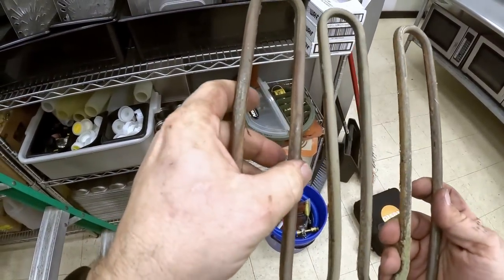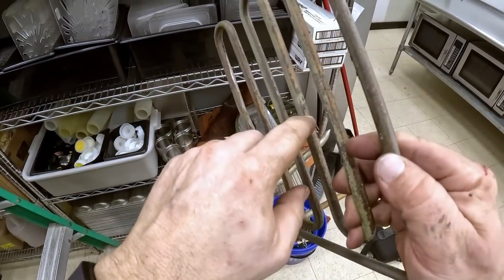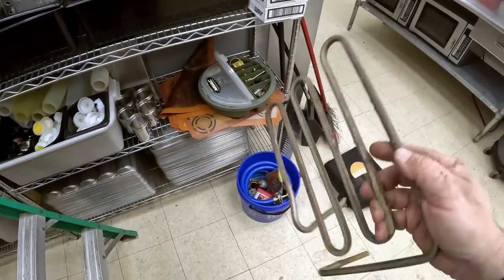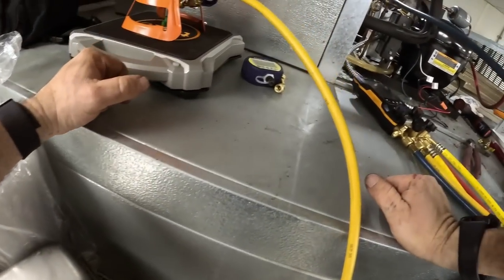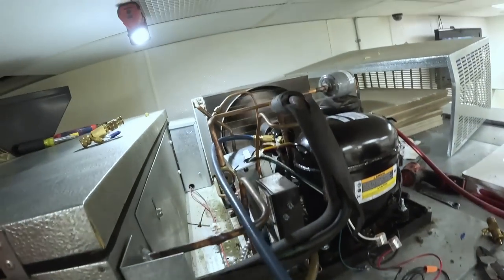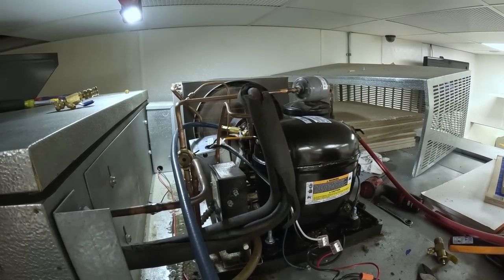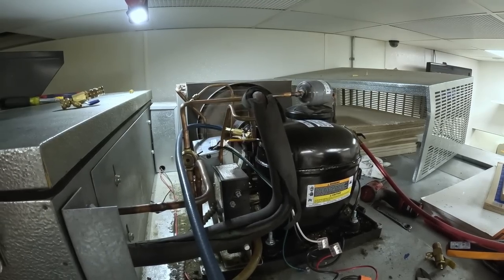That was supposed to look like metal. Silver on top, but copper on the sides. And you can see where some of that MC cable is hitting. We're flashing off on the sight glass, but we gotta give her a little bit. Let her stabilize here. Like I said, that filter dryer kind of bothers me a little bit because I'll get judged on that, I'm sure. But like I said, check out my other braze jobs and stuff.